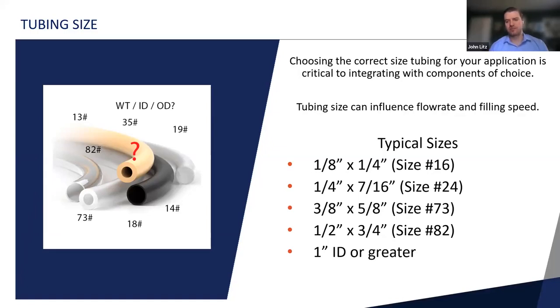For 1/8 by 1/4 inch, if you're doing any type of sampling, generally you might be using a small sampling port on a smaller size tube. If you're doing pumping upstream where you're doing scale up, you might see something like a 1/4 inch ID or 3/8 inch ID used. And then as you get further in the process, when you're doing larger volume fluid transfer, you'll of course be seeing larger ID tubes. So you'll be seeing more of those 1/2 inch or 3/4 inch or 1 inch ID tubing.